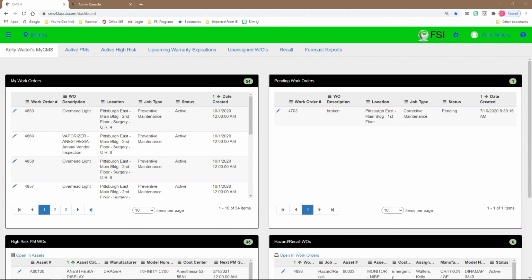A number of years ago, FSI standardized and tried to set up some standards and best practices for the facilities departments. Again, we're bringing them from paper. We wanted to show them some ways on how to set up their CMS to better suit them, using that electronic version. And so we set up a lot of standards. They were asset categories, statuses for work orders and statuses for assets, and those types of things. We did not, however, have a lot of standards for the clinical engineering groups.